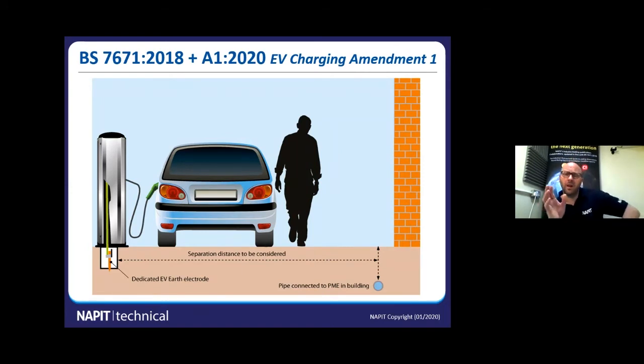If we imagine you've got PME supplied to the building over there on the right hand side, and you've got the service pipes under the ground going into that property. When they're inside that property, if they're metallic, they're more than likely going to be bonded to the PME, the MET. So if there is an open circuit fault, a lost PEN conductor, the pipework within the installation rises in potential. Within that, we have our equipotential zone, so that limits the effects. However, the pipework underground is also going to rise in potential. And now we're going to get a situation where we could have voltage transfer. If you have a look at that dotted line there, we could have voltage transfer from the pipe under fault conditions across to that electrode, and it could come back up to the charge point and onto the chassis of the car. So this is what we're talking about with TT installations.